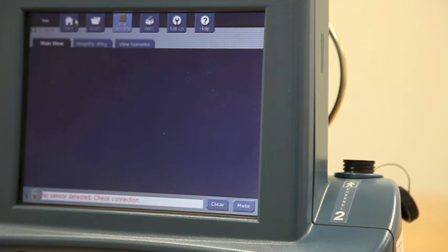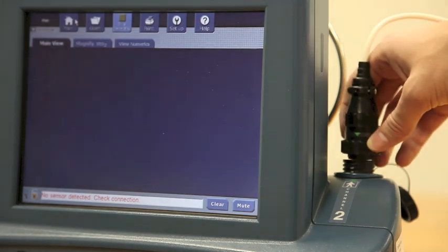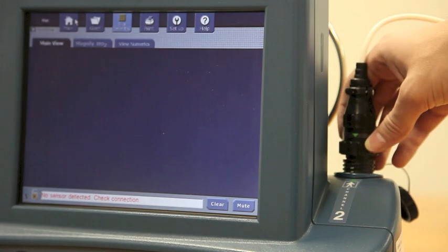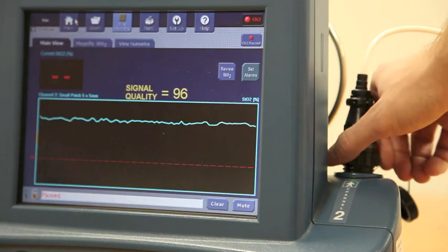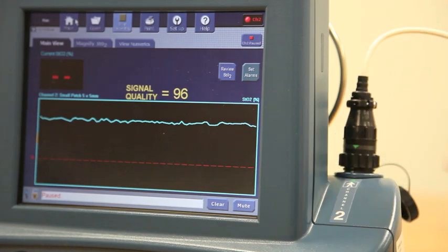The standard console configuration is a 2-channel option, Channel 1 and Channel 2, which can be used individually or at the same time. When connecting the sensor, notice the green arrow at the base of the connector and the sensor head. These arrows should be lined up when connecting the sensor. Once you have lined up the green arrows and felt the sensor insertion, simply turn the knob to tighten the connector. Turn the sensor to a snug fit. If the green arrow marks are not properly lined up, sensor damage is likely to occur.